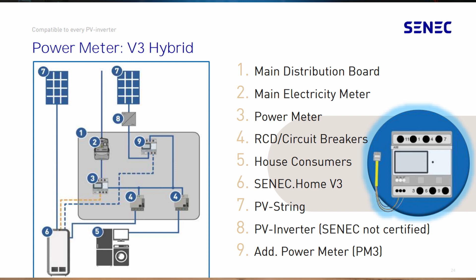There's quite a few brands, we've already run through them - I'll put them in the description below. Let's look at the next one, where you've got a non-SENEC certified inverter. You need another meter - you'd purchase what we call power meter 3, the one with the blue data cable, wire it in on the AC side of the inverter or inverters if you have more than one, and wire it back to the SENEC with the data cable.